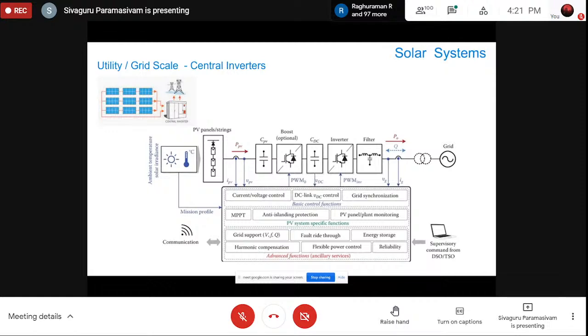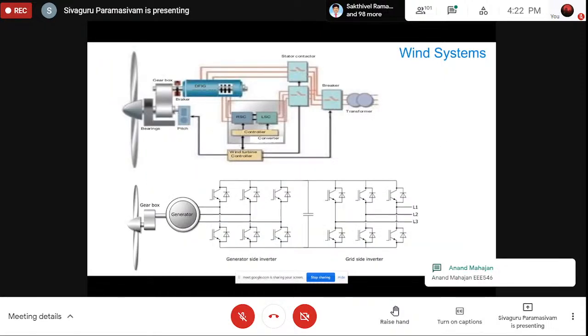And then we have other auxiliary functions, and then you can see there is a SCADA, that is a supervisory control, which we usually call SCADA, supervisory control and data acquisition, that is coming from the distribution service organization or transmission service organization. In our case, we can call that our TNEB or KSEB, depending upon whichever state we are working in. And you can also see there is a communication layer which is showing the symbol of a Wi-Fi. So all these data are then transmitted to a cloud, and I will tell why we are collecting all the information. I have a slide at the last to explain that.